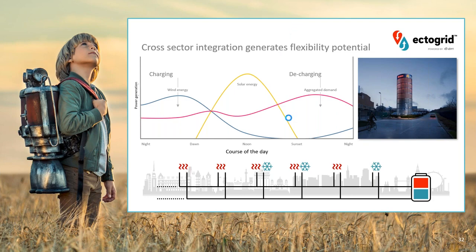Well, in general, this is the normal approach from a low-ex or an energy network with an ambient level that we are using here: a hot pipe and a cold pipe on ambient levels with booster stations in the buildings. The booster stations, i.e. reversible heat pumps that can generate heating and cooling, or we use a combination of heat pumps and cooling machines in or behind the heat interface units. The whole network is actually being steered by delta T optimization. So we really have to check the delta between hot and cold pipes in terms of temperature all the time. As I said, temperatures are fluctuating, they are flexible.